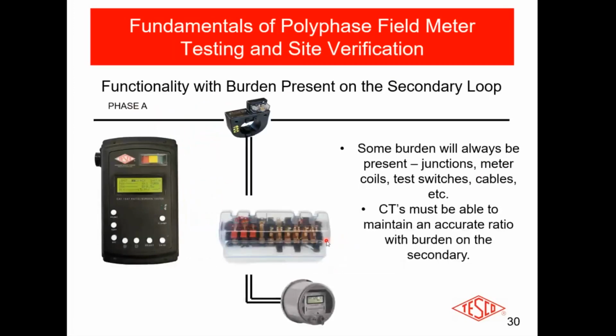All right? Now, what are we primarily interested in checking on an instrument transformer? We've got them all over the field. What are some of the things that we want? Well, one of the things that we want to do is check the burden. Why do we want to check the burden? Because that nameplate that you can't quite read over here tells me that it's 0.3, but only up to a certain burden, okay? If I exceed that burden, my accuracy goes down, all right?